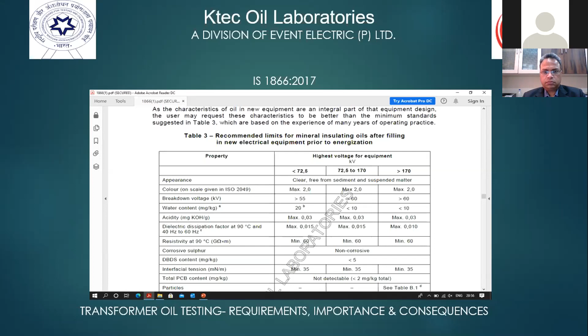If you see, for breakdown voltage, if we take the example of equipment with highest voltage of 72.5 kV and below, the breakdown voltage should be greater than 55 kV as per Table 3. If we come to Table 5 for breakdown voltage, you will see it is 30. So that means for energization of equipment, the breakdown voltage requirement is on the higher side. When we have energized that transformer and it has come into service, the requirement comes on the lower side. So the minimum requirement as per Table 5 is 30. Accordingly, these are the limits. It is very clearly defined in IS 1866. We need to see as per their requirements.